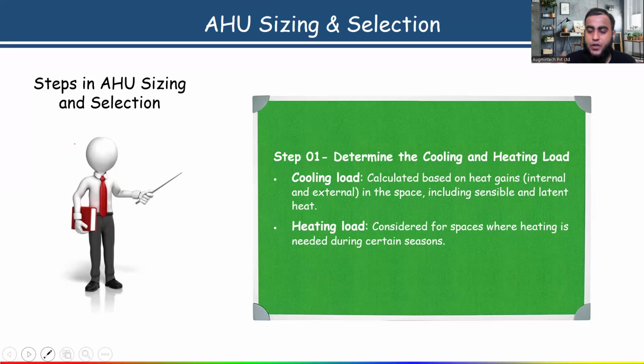Our main target is to find out the cooling load value in the summer season, and in the winter season, generally the heating load value. Our main target is to calculate the load, meaning for the AHU which we are selecting, how much capacity, how many TR, tons of refrigeration, the AHU needs for that space. So the first step is to determine the cooling and heating load. Now tell me, is it clear? Give me a reply, all of you. Don't keep quiet, please. Again, I'm repeating. Give me a reply. Is it clear? Okay. So now come to the next step.